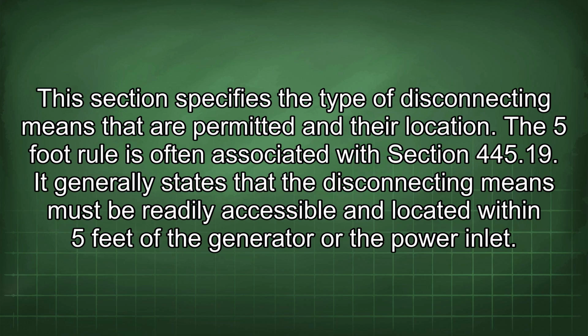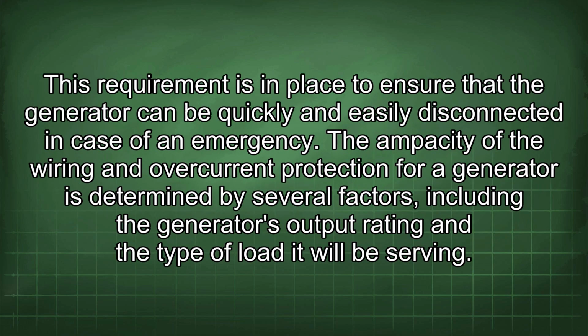The 5-foot rule is often associated with Section 445.19. It generally states that the disconnecting means must be readily accessible and located within 5 feet of the generator or the power inlet. This requirement is in place to ensure that the generator can be quickly and easily disconnected in case of an emergency.